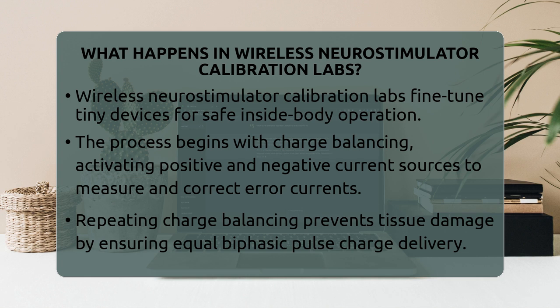The process starts with charge balancing. Technicians activate both the positive and negative current sources at the same time to check for differences. They measure the error current, which is the difference between the two, and then correct it. This step is repeated several times to ensure the biphasic pulses deliver equal charge on both sides. This prevents tissue damage caused by net ion flow.